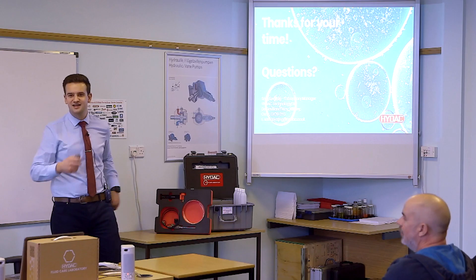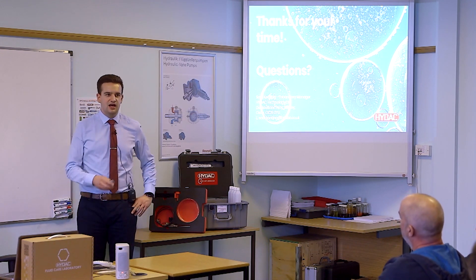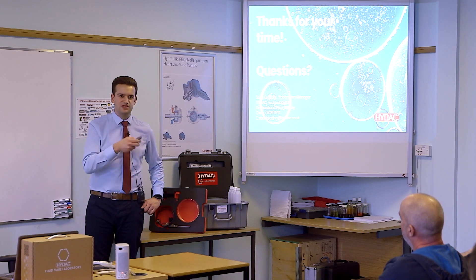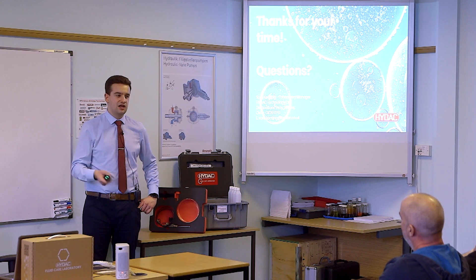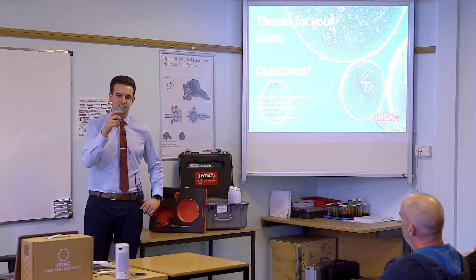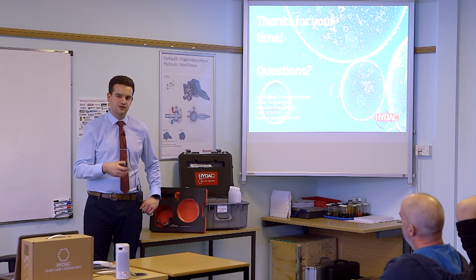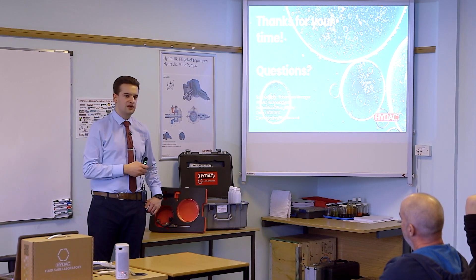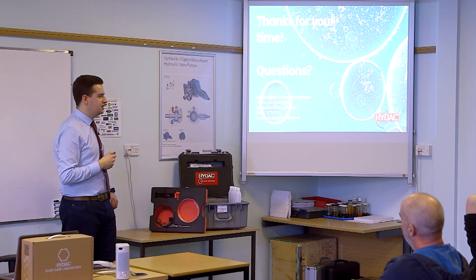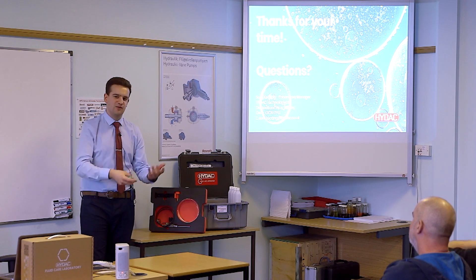Given the impact of temperature, would you increase the life cycle by moving to synthetic oils to be more resistant to temperature buildup? These more modern synthetic oils will be able to prevent oxidation from taking place to a certain degree. But again, because of the nature of them being non-polar, when the oxidation products do build up — which they will inevitably — then they will start to show signs of that more quickly. You'll see the symptoms quicker, they'll fall out of solution quicker. But in terms of extending the lifetime, yes, they would extend the actual lifetime. The antioxidant additives would help to combat that for a longer period of time.